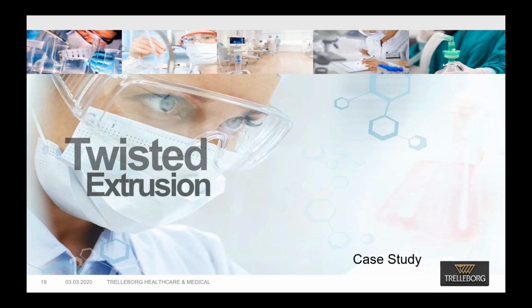The twisting lumen create longer wire lengths at bend locations to distribute the dynamic bend loading more evenly across the conductor. This is in comparison to non-twisted tube, where the conductor on the outer radius of the bend sees higher loads and is more likely to fail over the millions of bend cycles that occur during the life of the implant.